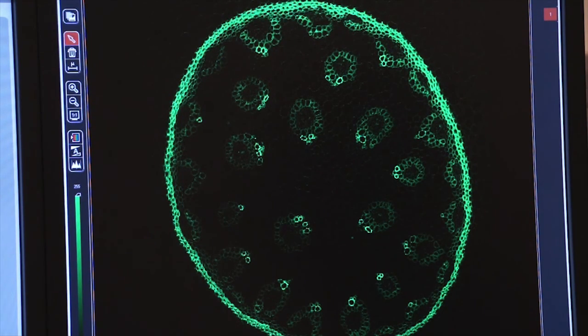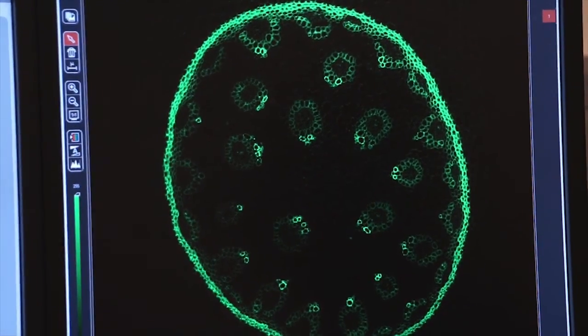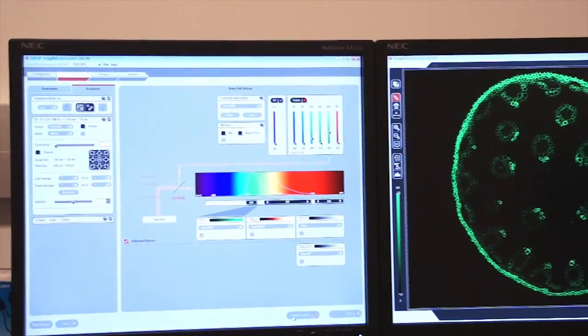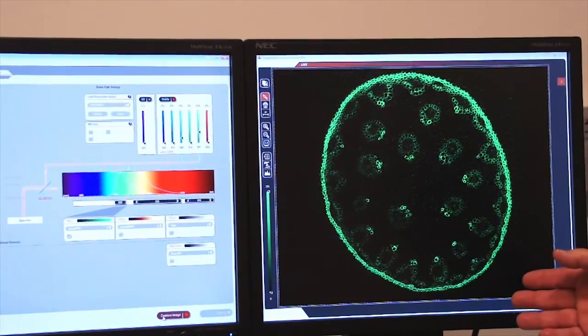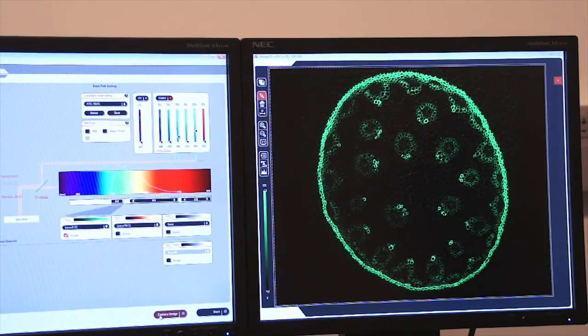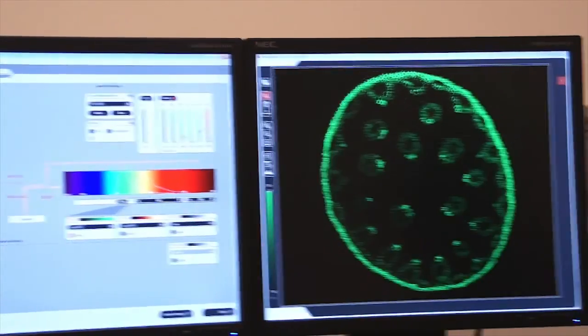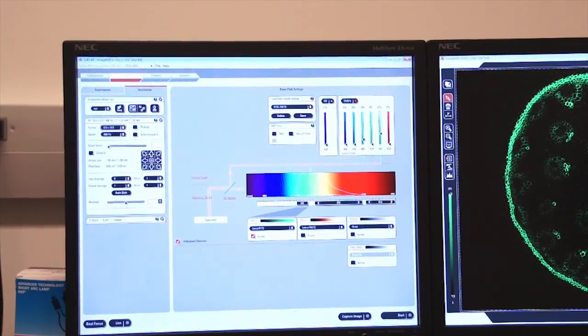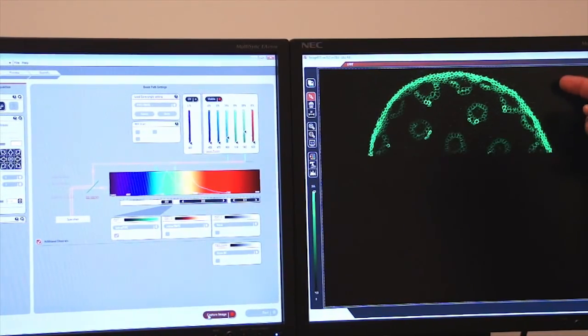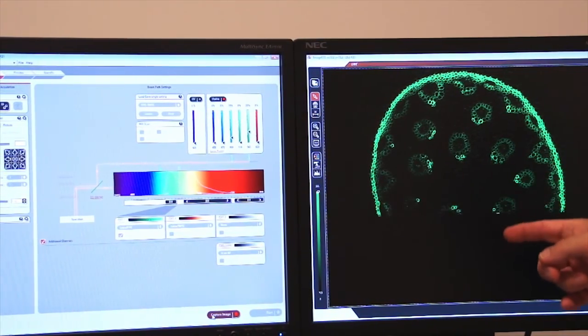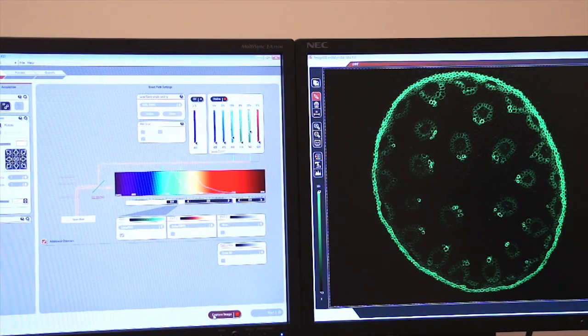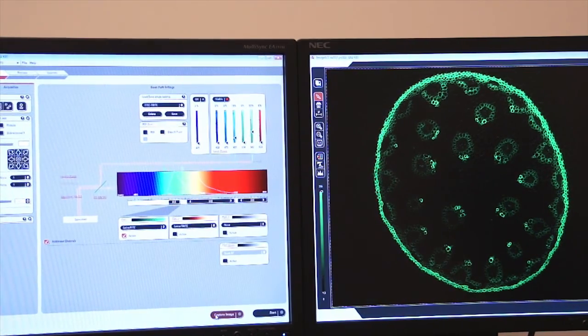So let's switch back to one. We'll do capture image. You see how fast the image is collected, but it's a grainy image, low resolution. So if I select, again, six line averages, I've told the system to capture me an image, but average out those lines and you can see a lot of that background noise goes away. I get a nice high resolution image using line average.